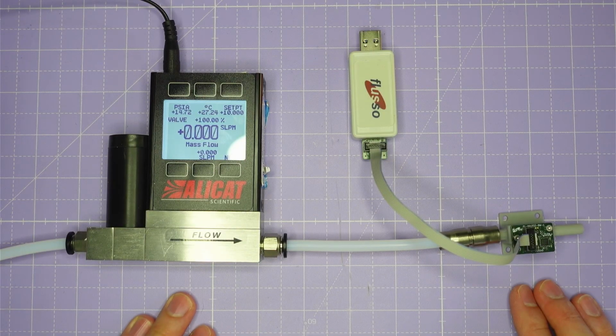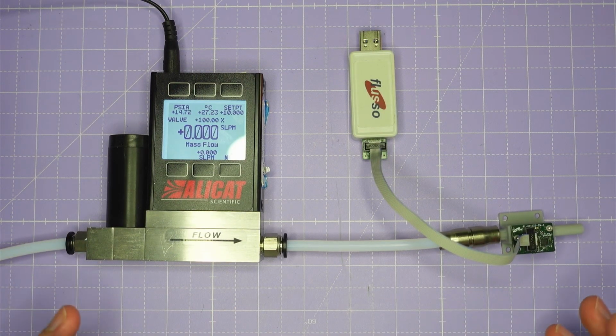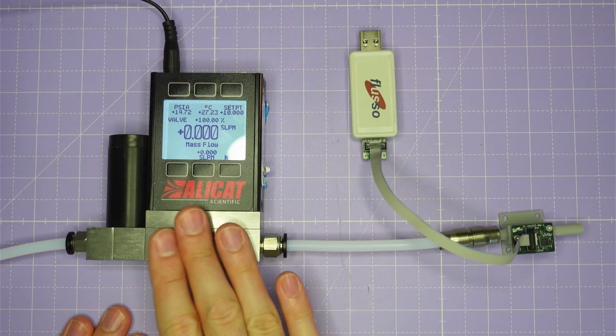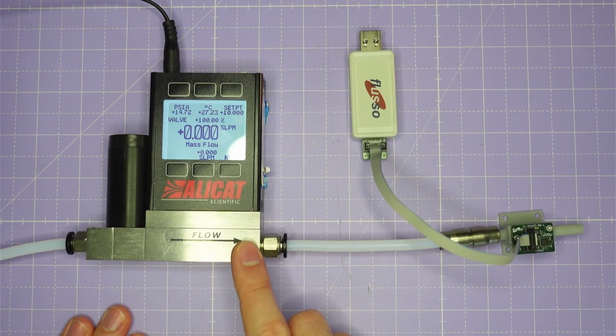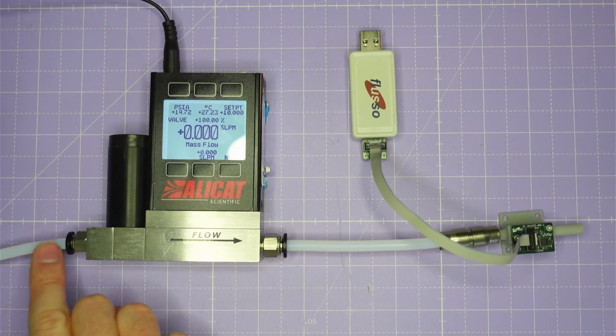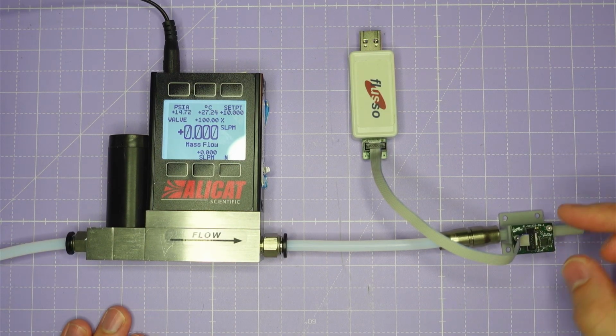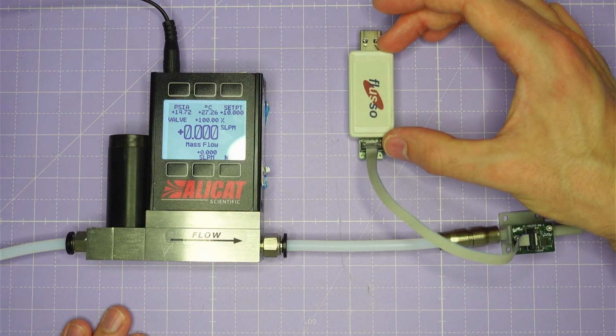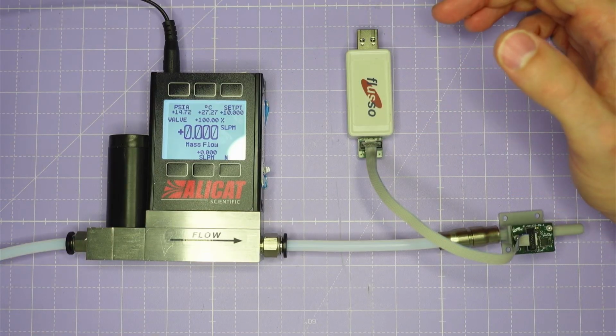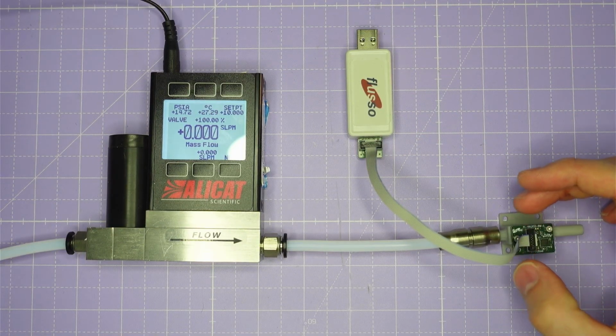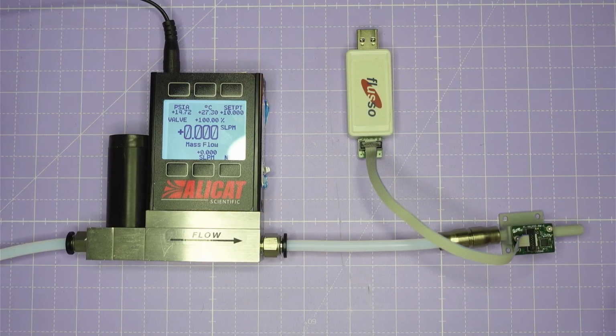To calibrate your FSE-112 module, you're going to need a test setup similar to what I have here, with a reference flow source. In this case, I'm using an Alicat mass flow controller, a source of air, and some way to communicate with the module. So here I'm using the Flusso USB to I2C adapter, but you could communicate with the module over any I2C capable device, for example, the host microcontroller in your product. Once you have the setup like this, you're ready to calibrate the sensor and achieve exceptional accuracy in your system.